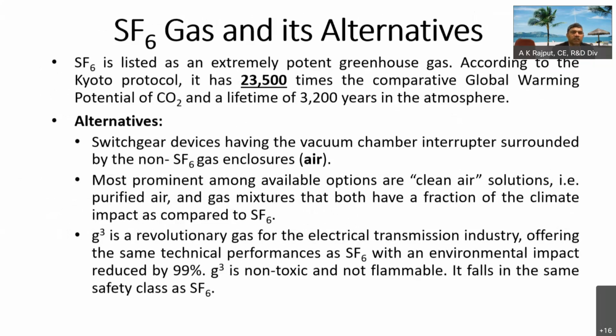Then SF6, we have talked. Now it is my duty to tell you that 1 kg of SF6 is equivalent to 23,500 times the global warming potential of 1 kg of CO2. This figure has now been updated by UNFCCC, and now this figure is 25,200. So the world is very serious. The European and American world is more serious about this SF6 replacement up to a certain voltage, because a sudden jerk cannot be given, and if the technology does not exist, how could things be installed.